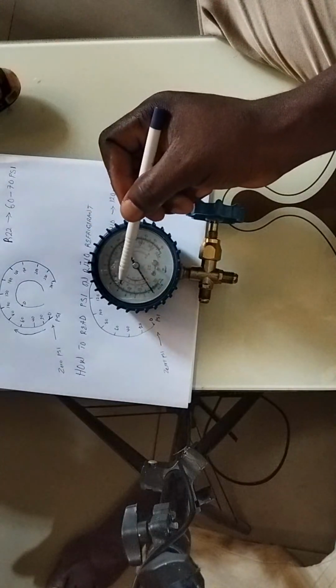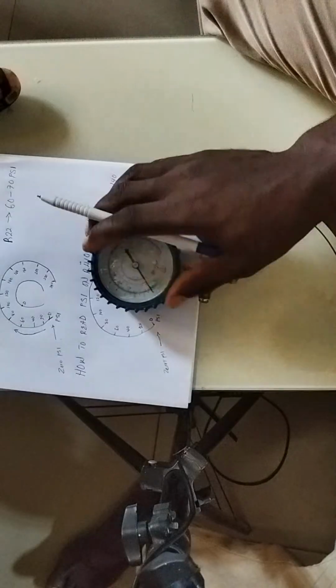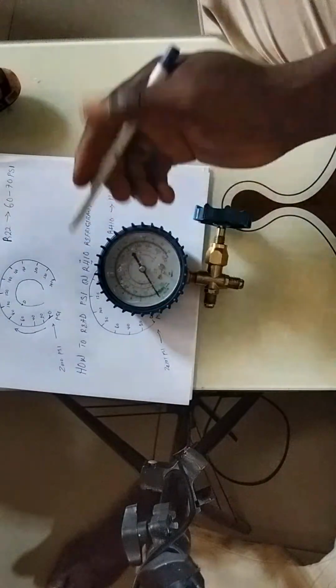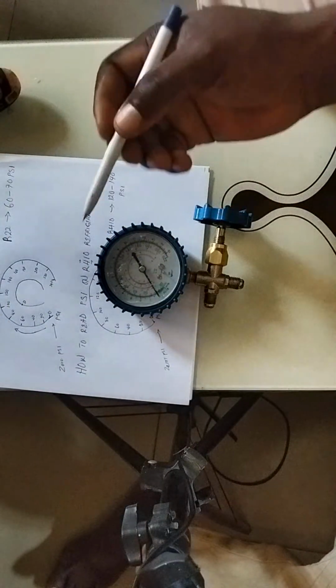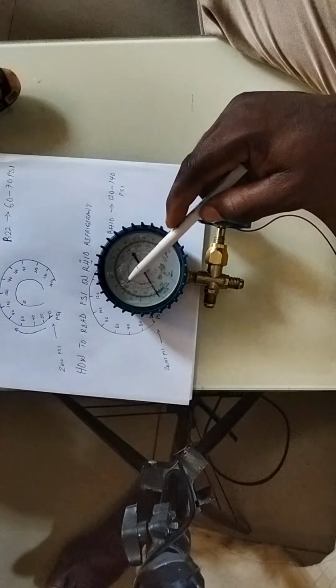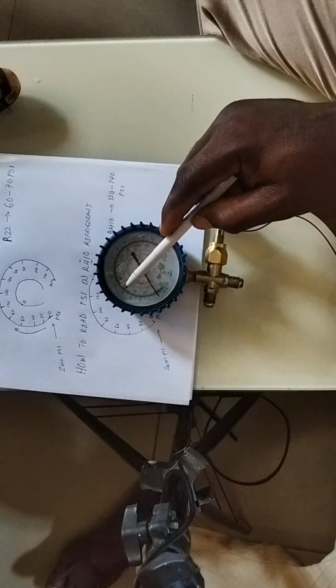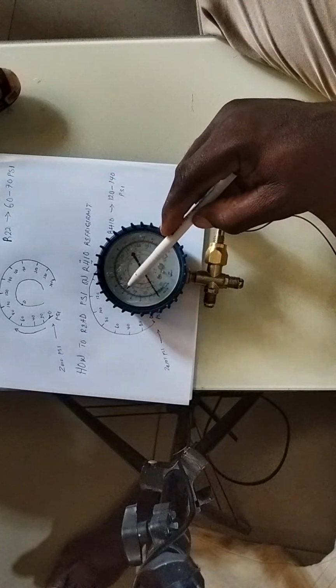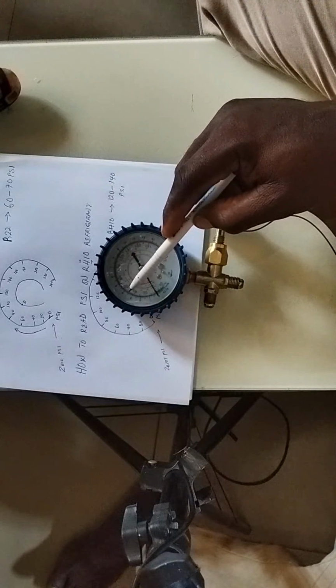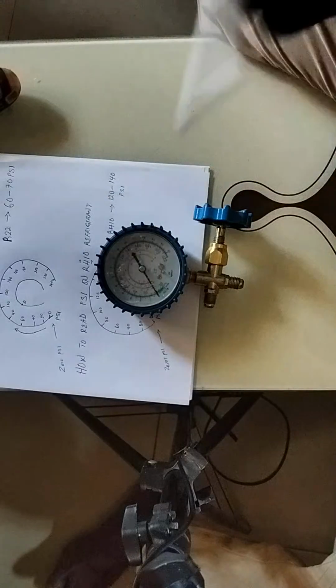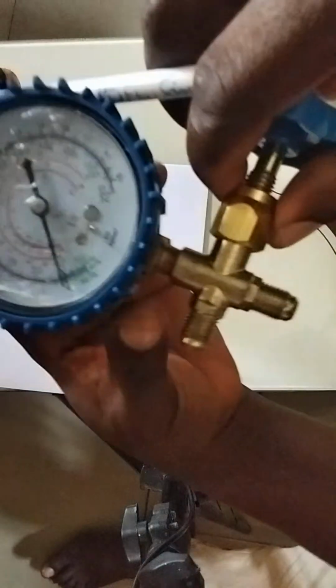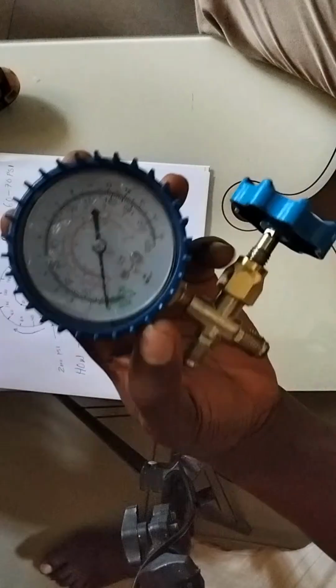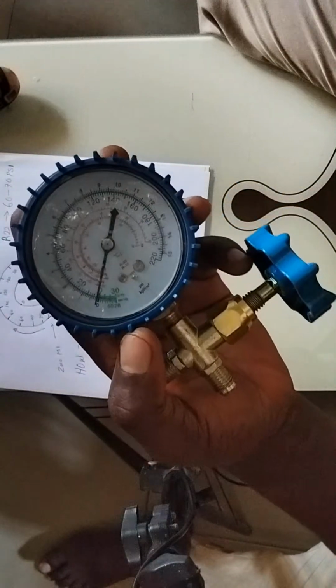If you set up your gauge and it gives you 60 psi, you allow it there for like 20 to 30 minutes. If there is a leakage on the system, when you come back, you will notice that there will be a psi drop either by 1 unit, 2 units, 3 units, or 4, depending on what you notice on it. Understand? Depending on what you actually notice on the system. So that is just it.